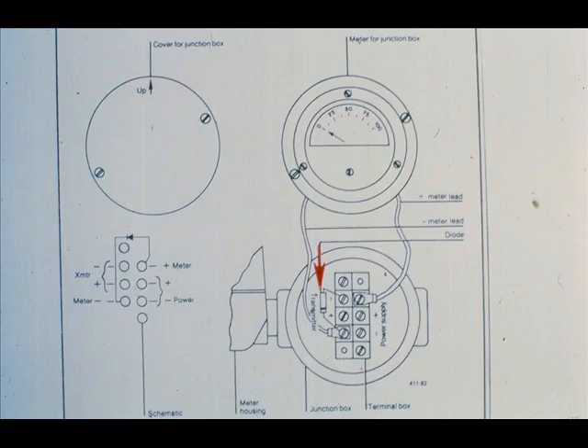Other receivers in the loop are connected in parallel across the range resistor. If the transmitter has a local indicator, the circuit should be protected with a diode. In case the indicator opened up, the diode would conduct and the loop current would not be interrupted.